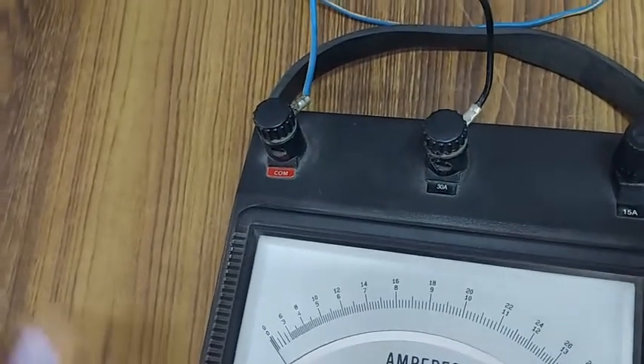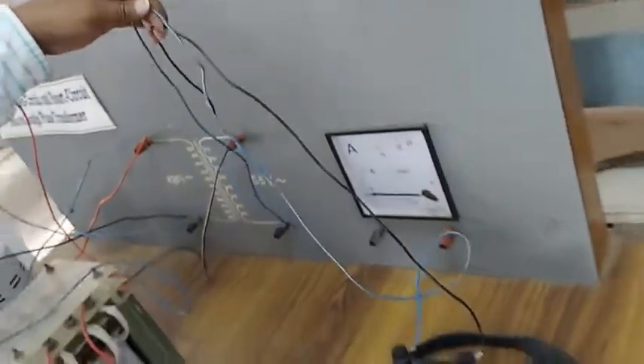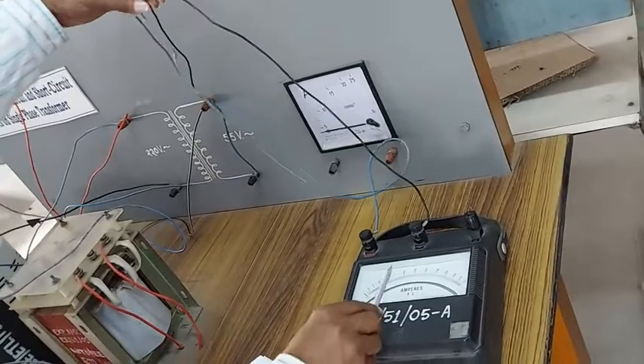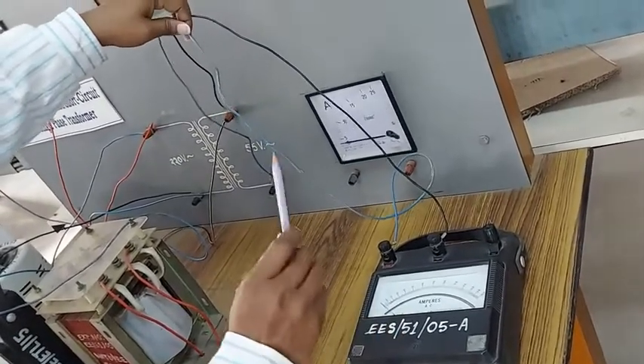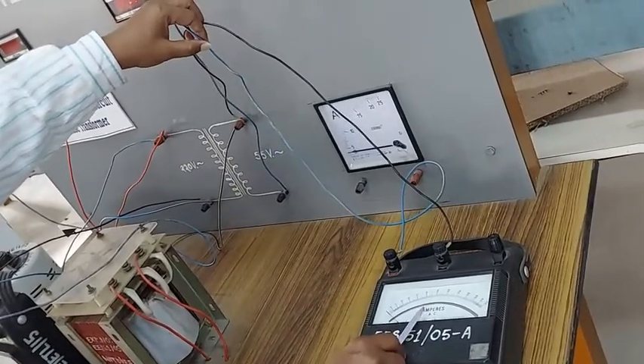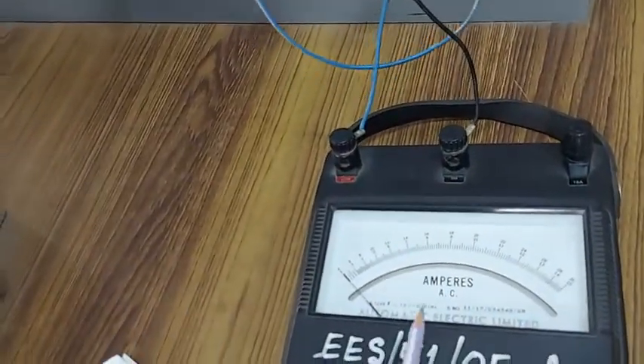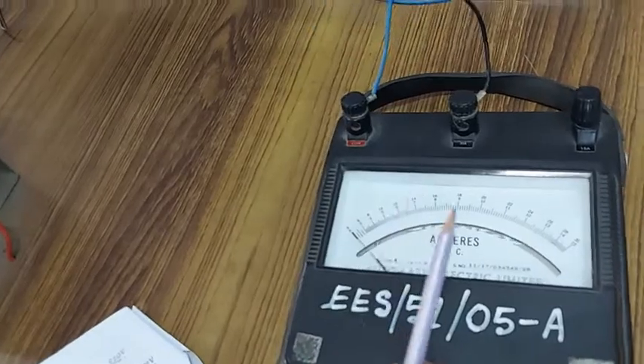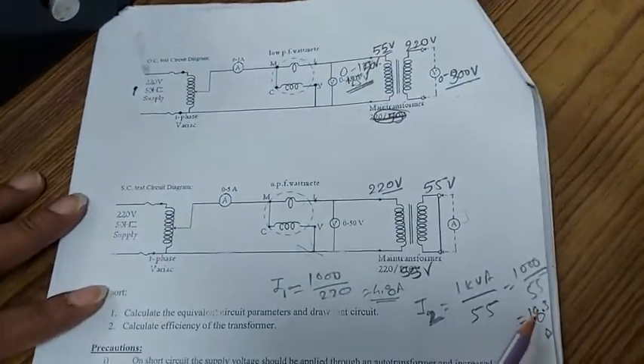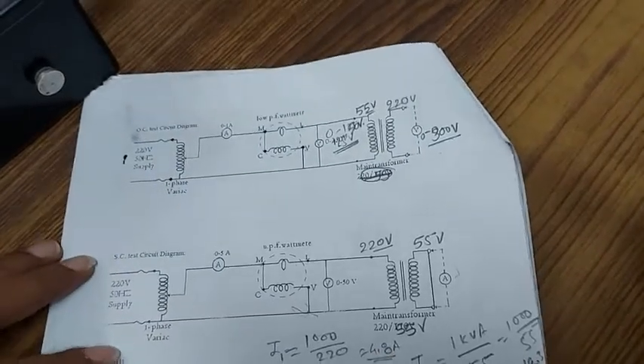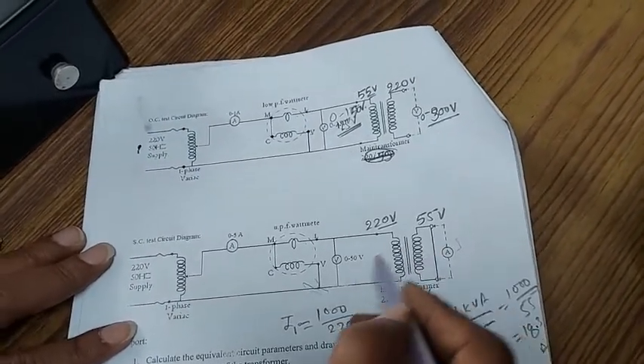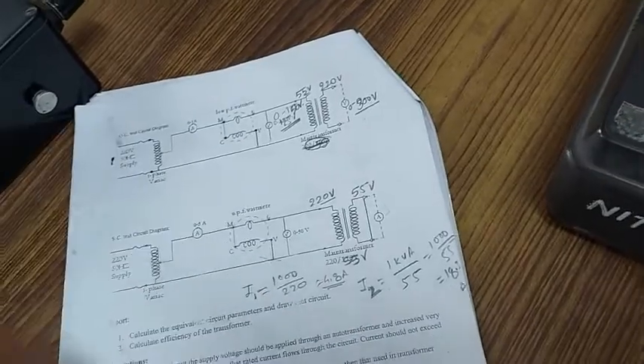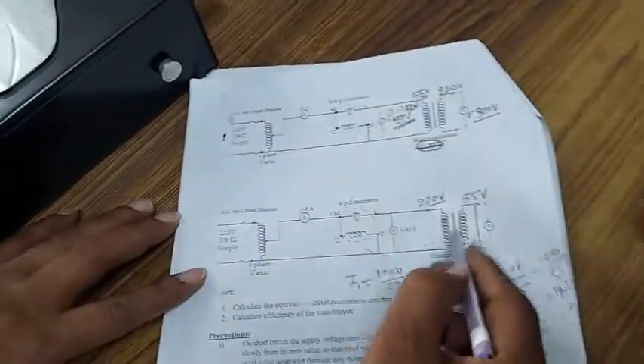So secondary side is also connected by one ammeter, and that ammeter is used to measure the secondary short circuit current as well as to make the secondary shorted, because ammeter has very less resistance, so definitely it will work as a short circuiting element, and that current will be 18.18 or 18.2 approximately ampere will be flowing at the condition when the 5 to 15% voltage of the primary is applied.